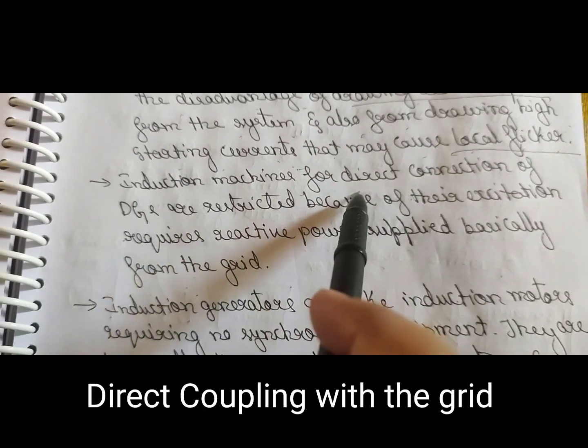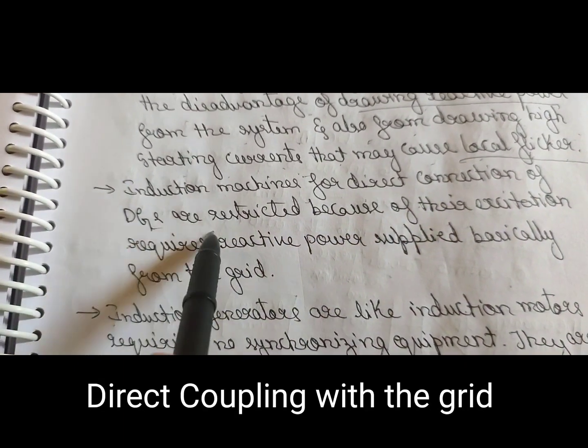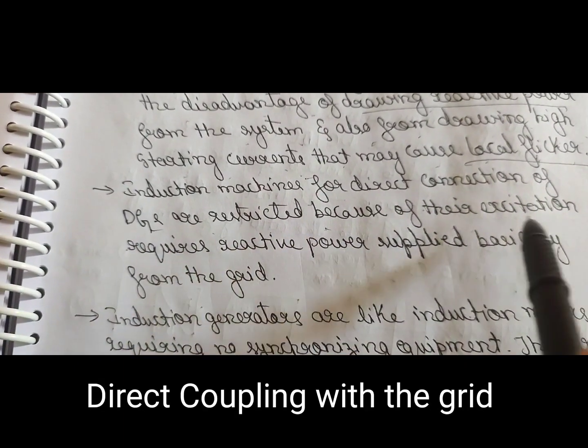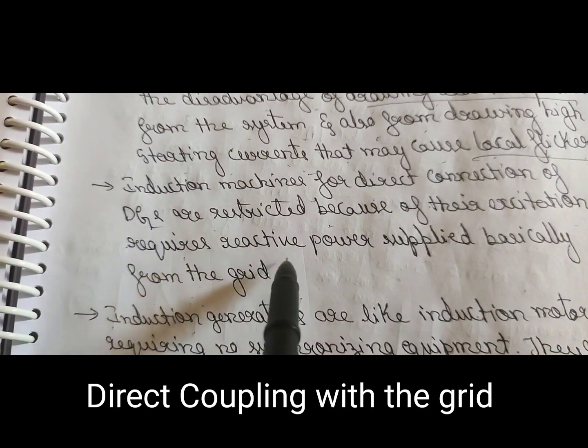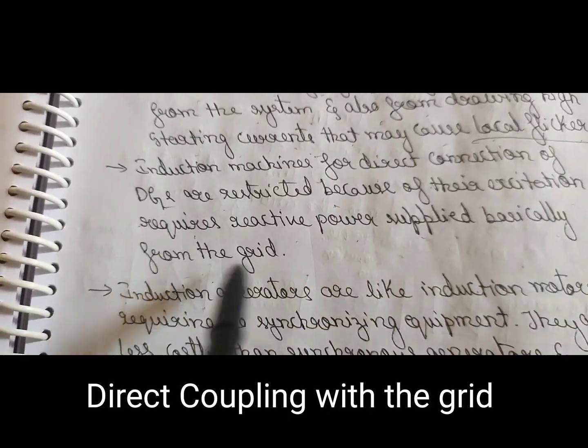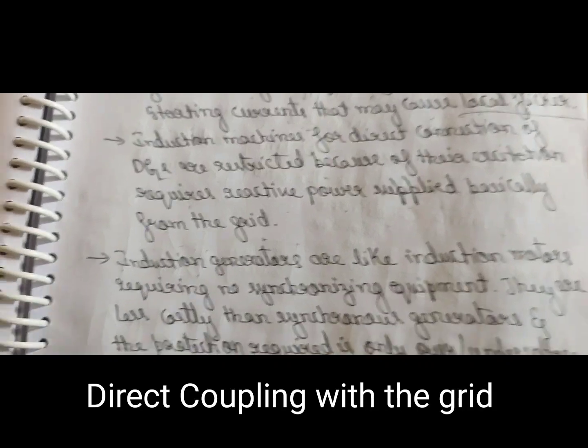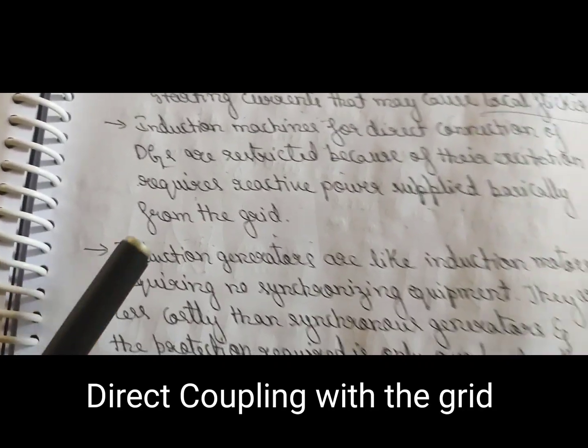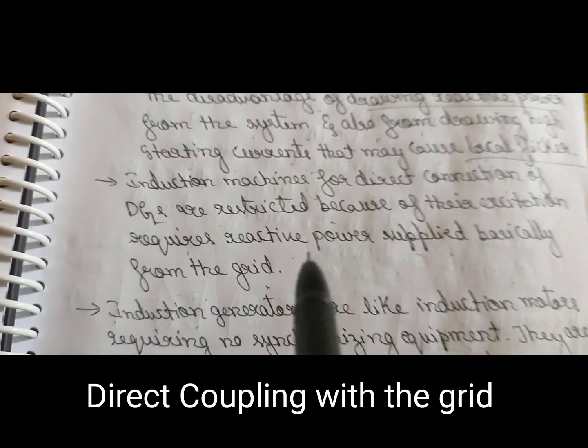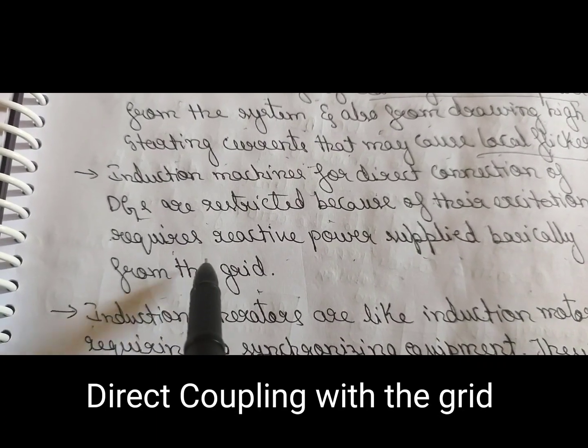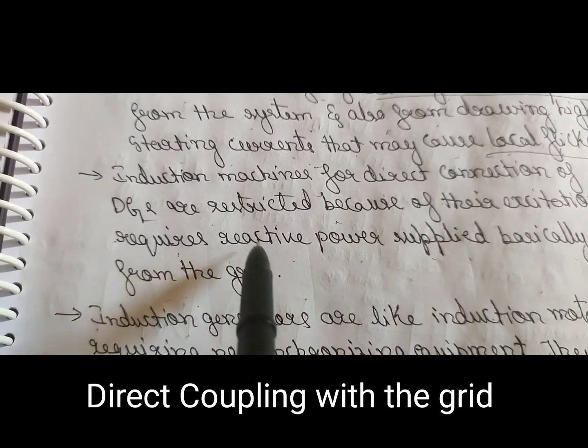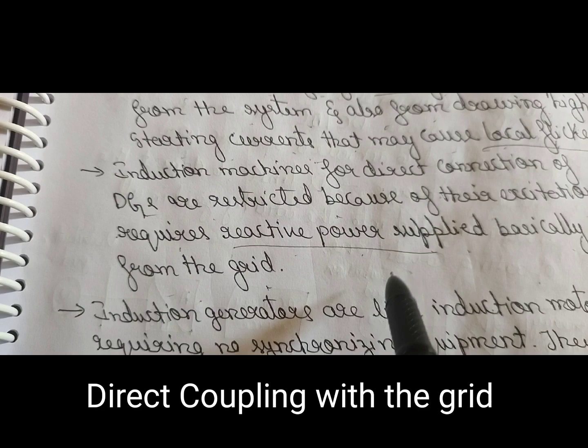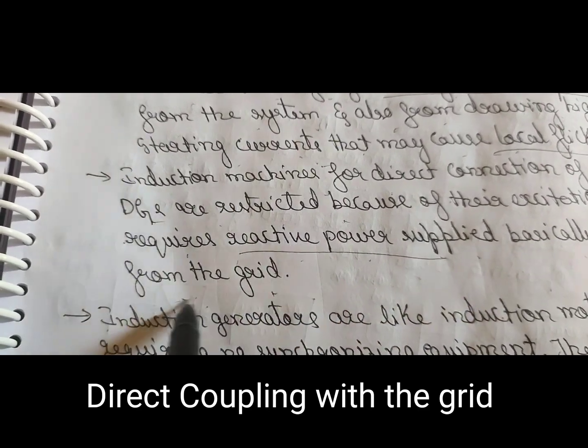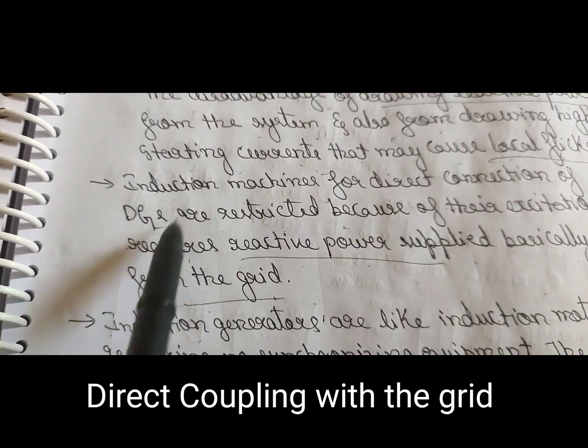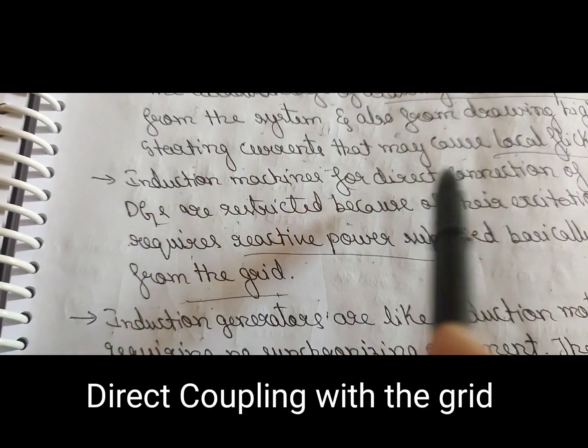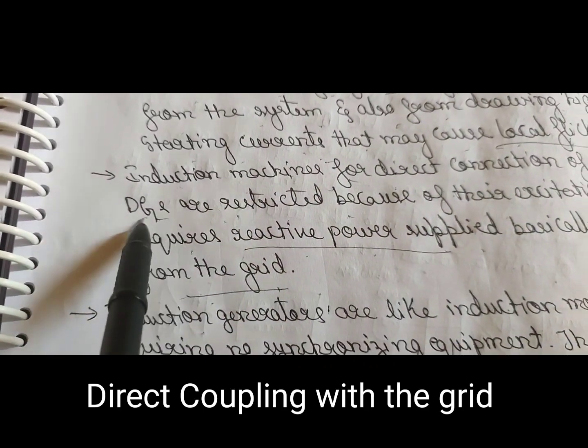Induction machines for direct connection of DGs are restricted because their excitation requires reactive power supplied basically from the grid. So why do they restrict induction machines? Because their excitation requires reactive power, which needs to be supplied from the grid. That's why they restrict induction machines for direct connections of DG.